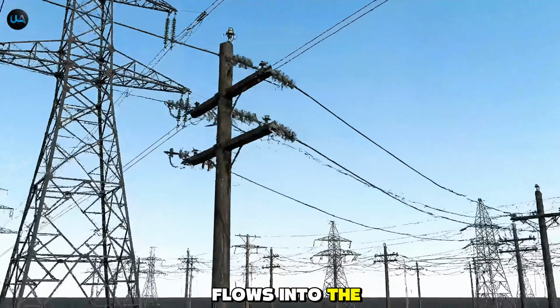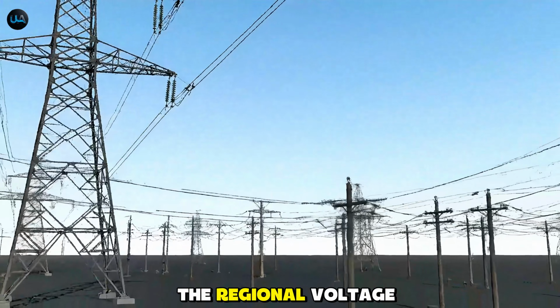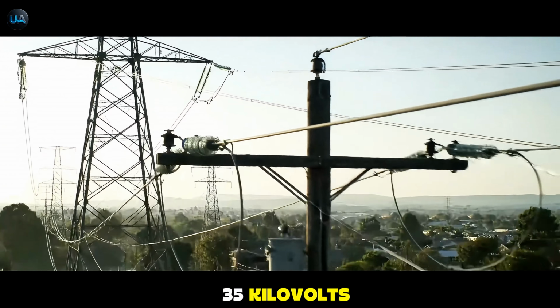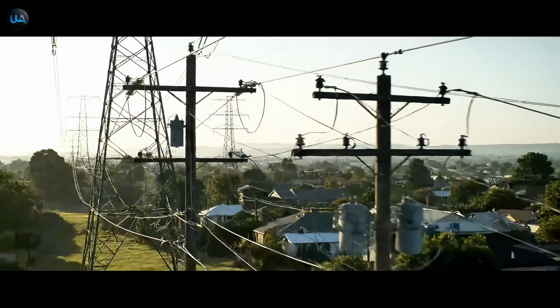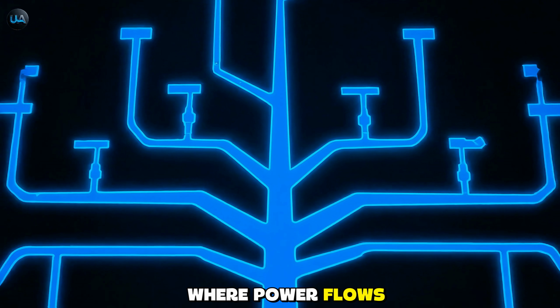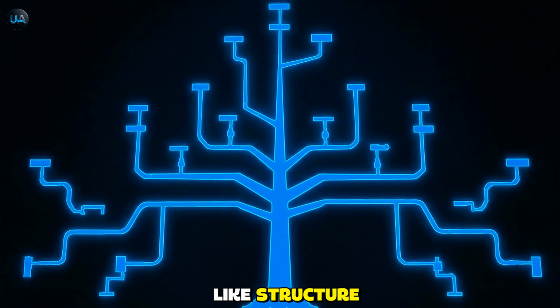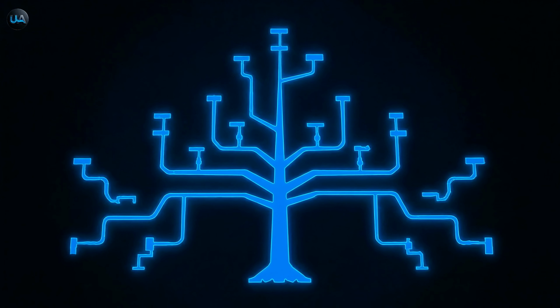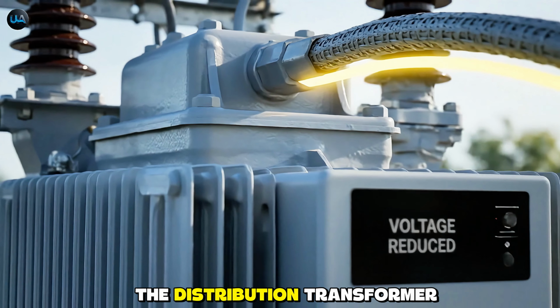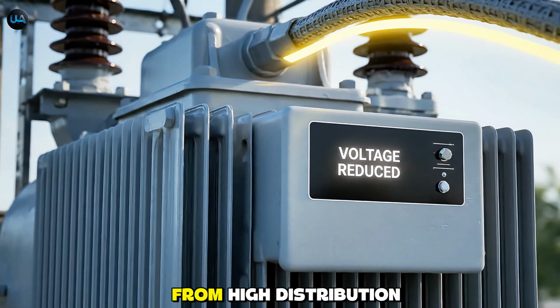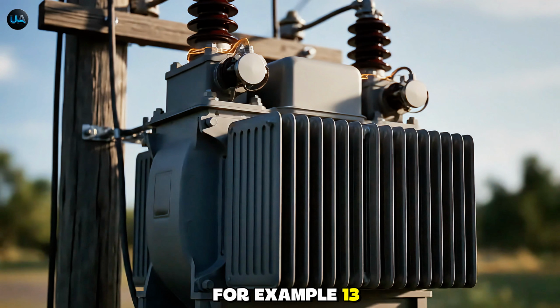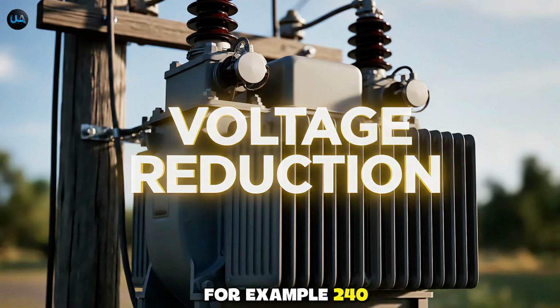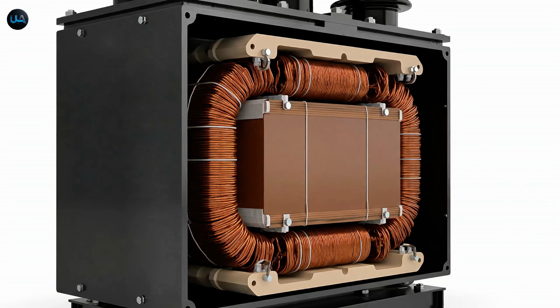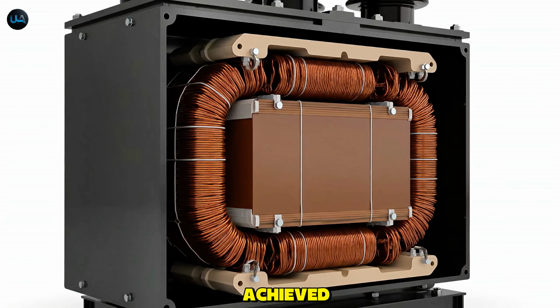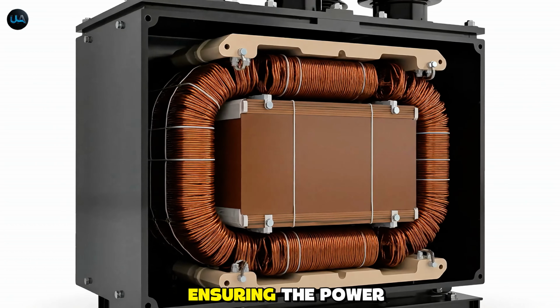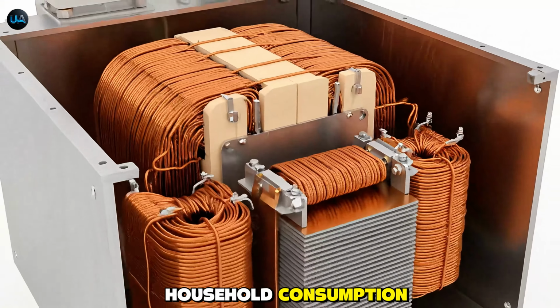The power now flows into the distribution system. This network takes the regional voltage, 13 kilovolts to 35 kilovolts, and delivers it to local neighborhoods. This is the radial system, where power flows outward from substations into a tree-like structure, serving thousands of local customers. At the street level, the distribution transformer performs the final critical step-down from high distribution voltage, for example 13 kilovolts, to low service voltage, for example 240 volts. Inside, this final step-down is achieved with the highest turn ratio difference, ensuring the power is safe and ready for household consumption.